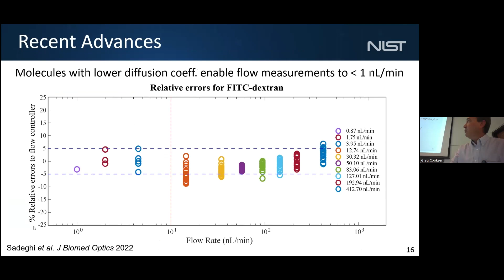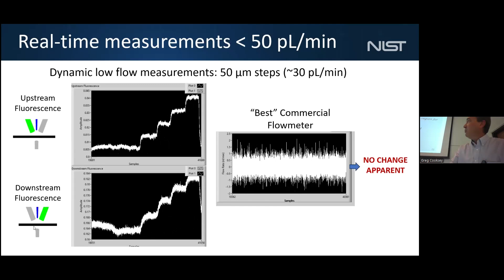And just to show you the demonstration here, we're taking 50 micron steps of this water column, and you see on the left measurements from the upstream fluorescence detection and the downstream fluorescence. That gives us the polarity of the flow. And on the right, you see the world's best commercial flow meter showing no apparent change. So effectively, these steps are 30 picoliters per minute in real flow volume, according to the calibration of the conductance of the system. And this is in real time. So we're making really accurate, really quick measurements of flow within this system.